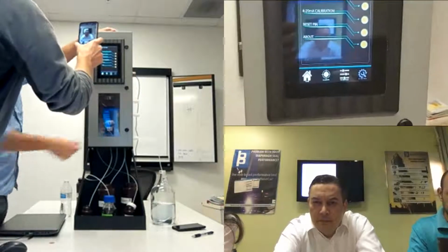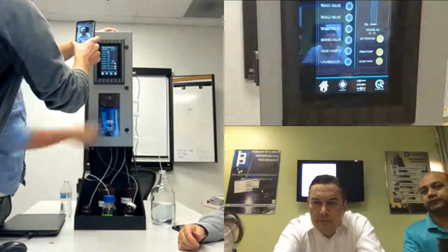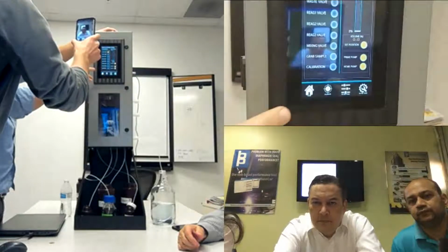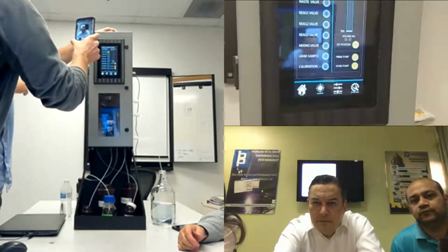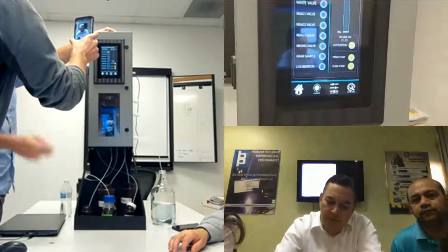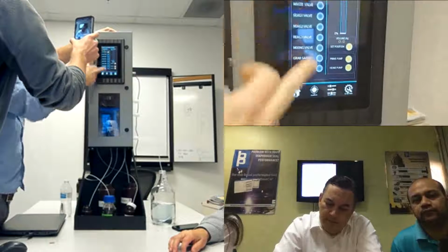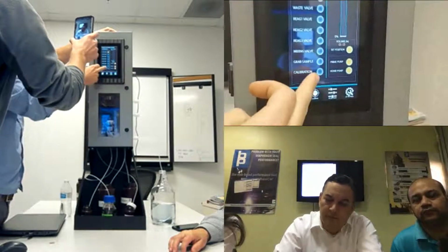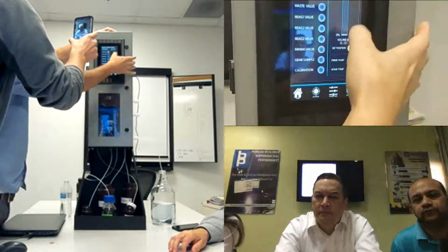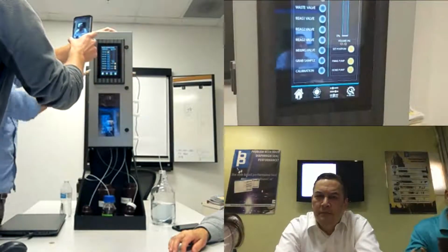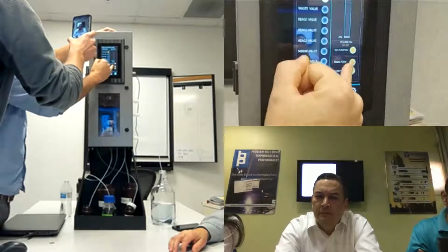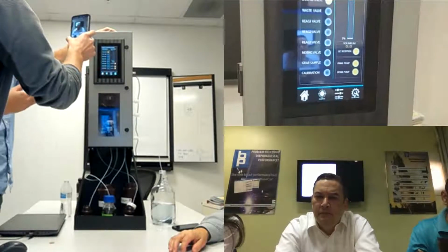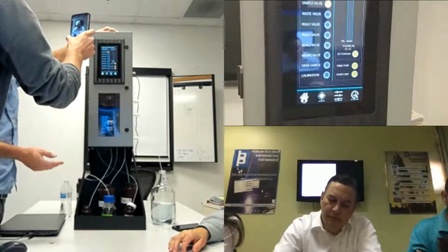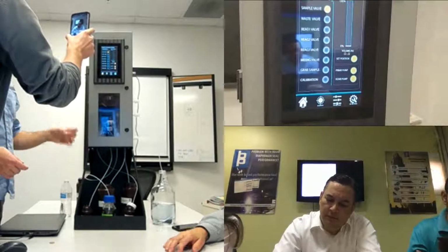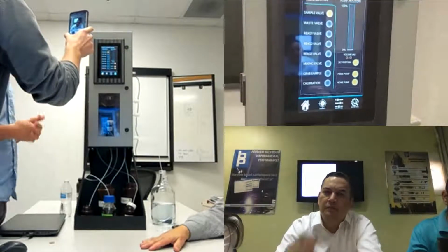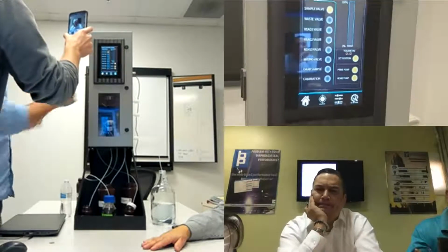In a deeper settings screen here, you're allowed manual control. So if there was an event where we need to do some diagnostics or test something a little abnormal, you can manually choose which valve you'd like, with which reagent. You can manually manipulate the pump position itself, and use lower level features such as priming the pump. It's an automated feature that will pull in if you're going to replace the reagents. It will automatically prime all the different reagent bottles for you with just a touch of one button. Okay. So that's a nice feature.